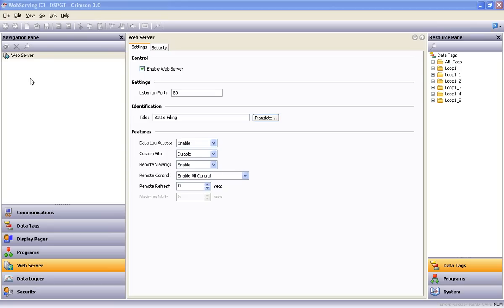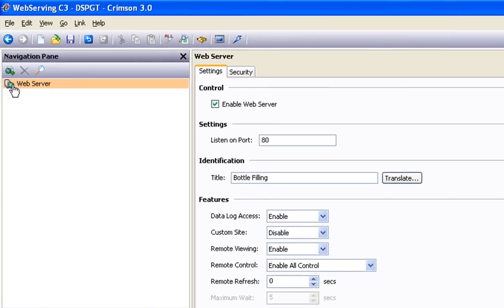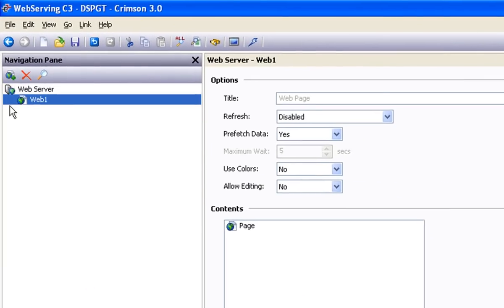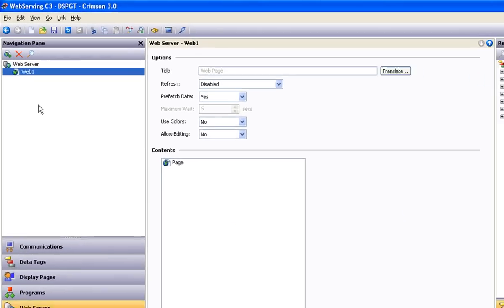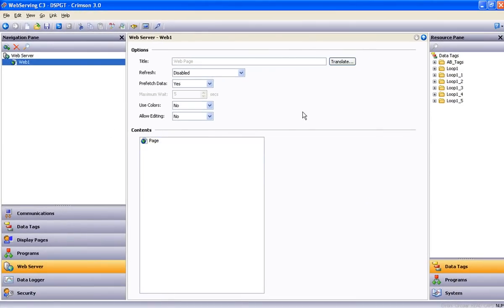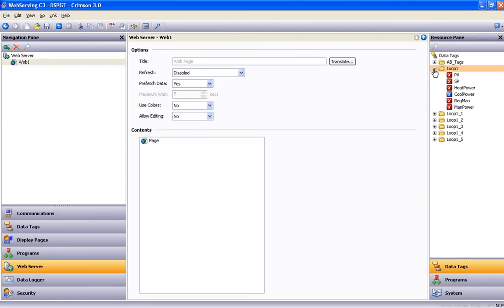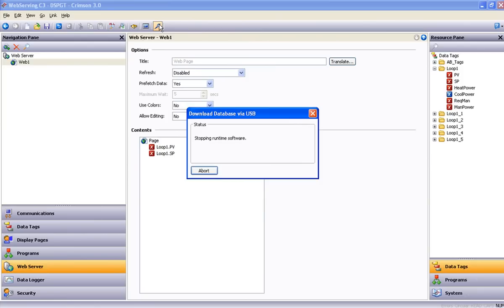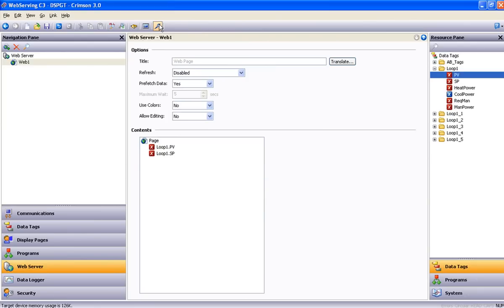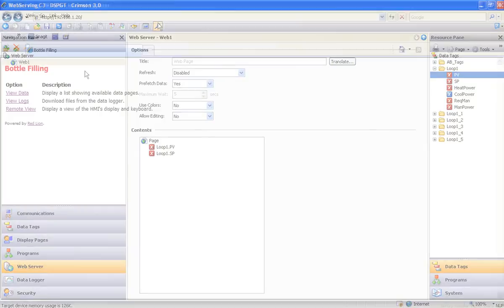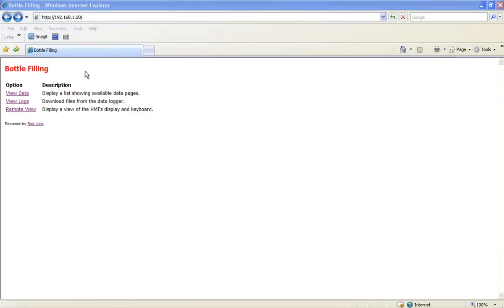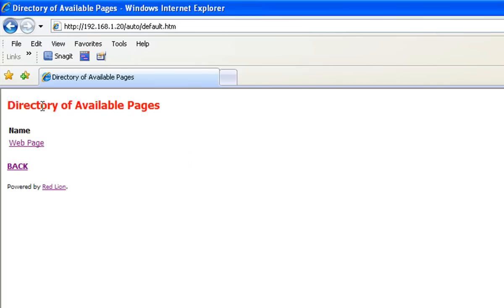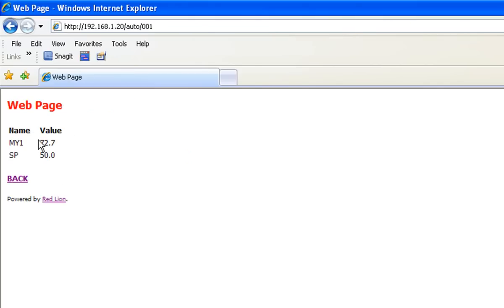What we can do to solve this little problem is create a page under the web server, or a whole list of pages if you like, and then come over here to the resource pane to the list of available data and drag onto that page what you want made available to the server. Then we download that to the data station. And now you can see there is an extra link available called view data. And if I click that link, my page or list of pages shows up here, and then I can view the data that I added to this page without viewing all of the graphics that are included with the remote view.